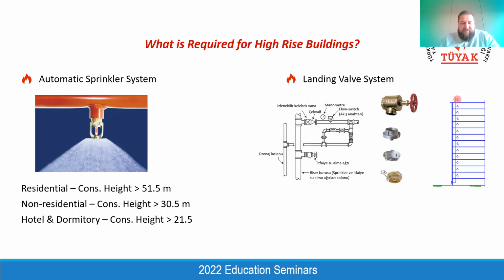That's why the architects should ask the investor whether they have knowledge about the sprinkler or landing valve system requirements in the fire code, and then you decide the exact construction height during your project. And for hotels and dormitories, it's a little bit different. They are separated from the rest of the building. If the construction height exceeds 21.5 meters, the sprinkler system becomes mandatory as per the Turkish fire code.